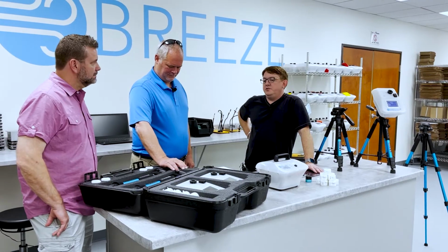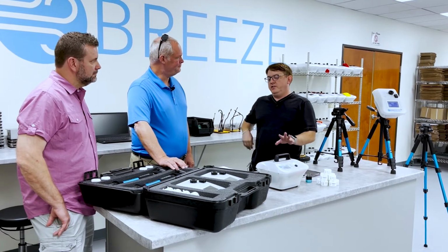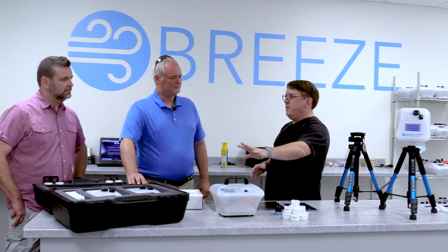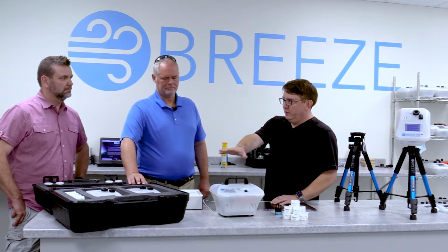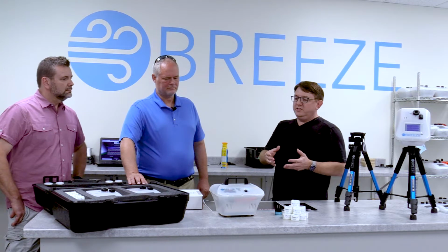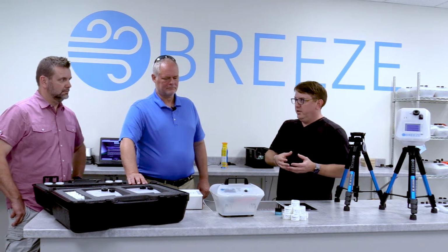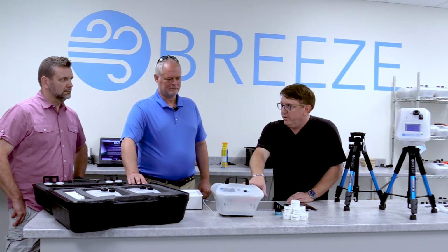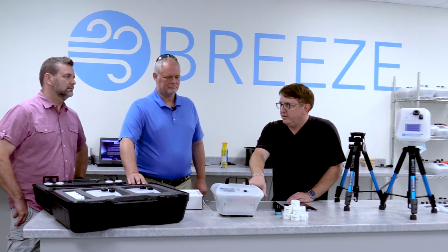It's not a recommendation, and just to be clear, let's use words here. This is a monitor for radon. That's a tester for environmental. So vacuum pump, radon testing unit, a continuous radon monitor with a chamber within it. As far as these go, these are calibrated every single year. You have to send these back to us.